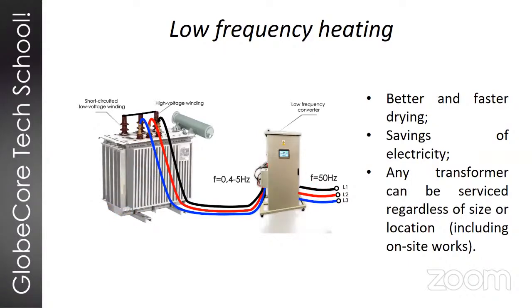The quality of insulation when using this method is increased significantly compared to more traditional systems that use, for example, vacuum drying or hot air. This is due to the fact that in the low frequency heating process, the source of the heat is the winding itself, which is the ideal place to apply heat to extract water from insulation. The duration of the drying process is reduced quite significantly compared to regular systems which use hot air and vacuum, and in turn it allows us to save up to 50% of energy.